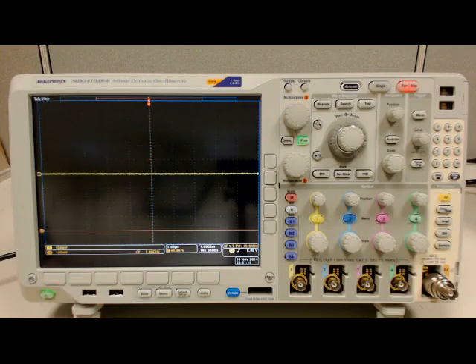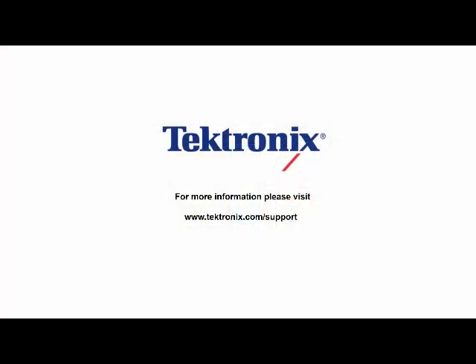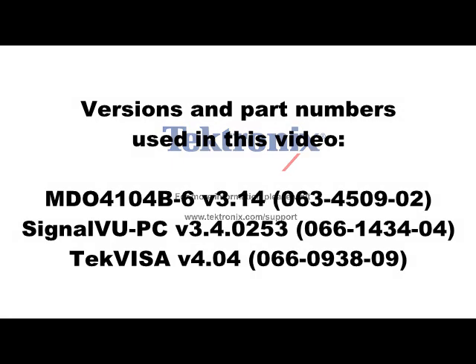Disconnecting the instrument is extremely easy. Simply close SignalVU-PC, press Default Setup on your oscilloscope, remove the USB cable, and you're done — all disconnected. Thank you for watching, and please contact us at www.tektronix.com/support with any further questions.